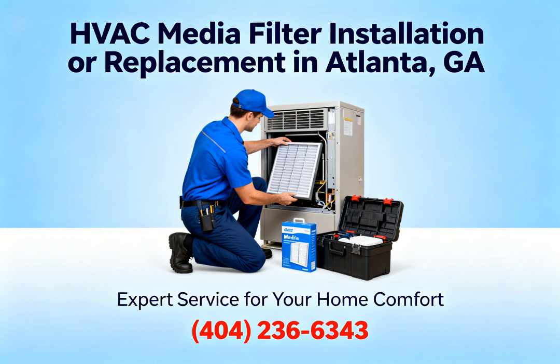And this density is measured by the MERV rating, the minimum efficiency reporting value. Right, I've seen that on the packaging. Yeah, so standard 1-inch filters hover around MERV 4 to MERV 8. High-capacity media filters operate in the MERV 11 to MERV 16 range. Which is a huge jump.